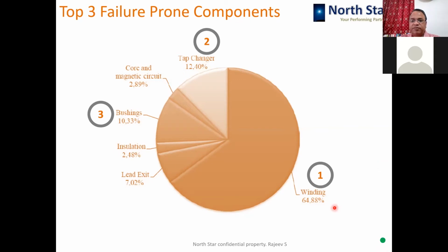So that's why winding failures are highest, followed by tap changer failure. It is 12.4%. OLTC and OCTC, off circuit tap switches, are the weakest link, we can say, in the transformer. Those are the only components which move, otherwise everything else is stationary. So tap changers, because of their nature, because of the kind of function they perform, are liable to fail more, and this further gets aggravated if they are not maintained properly. If the maintenance is overlooked, then the OLTC fails further.